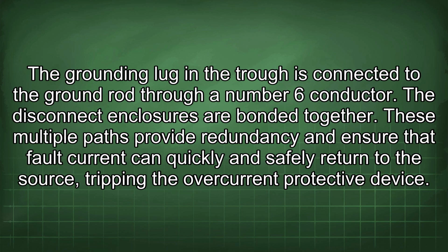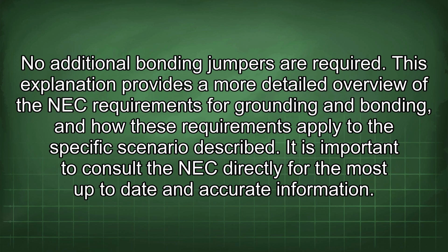The grounding lug in the trough is connected to the ground rod through a number 6 conductor. The disconnect enclosures are bonded together. These multiple paths provide redundancy and ensure that fault current can quickly and safely return to the source, tripping the overcurrent protective device. No additional bonding jumpers are required. This explanation provides a more detailed overview of the NEC requirements for grounding and bonding, and how these requirements apply to the specific scenario described. It is important to consult the NEC directly for the most up-to-date and accurate information.